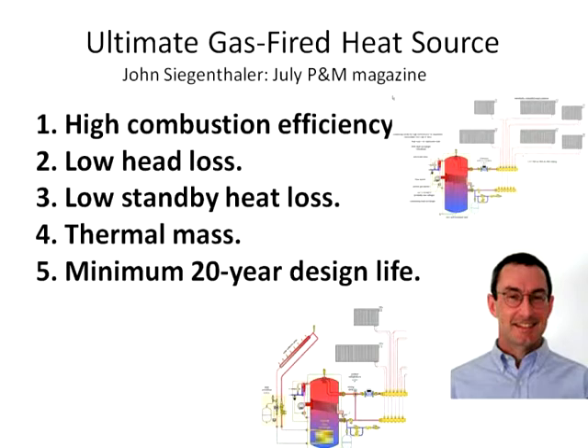Now, he didn't know that the Evolution was in the making at that time. So actually what he did, particularly in the April article, is he came up with a design almost exactly like what the Evolution is. And then he came up with further designs which are variations on those themes. Why? Because he wanted to meet certain criteria. Now, the high combustion efficiency is without question. We've had independent testing by PG&E, which shows us substantially more efficient than our competition, condensing water heaters. Low head loss. Now, let's face it, when you have a water tube type low mass boiler, the pressure drop of going through that heat exchanger plus through an indirect water heater is substantial.